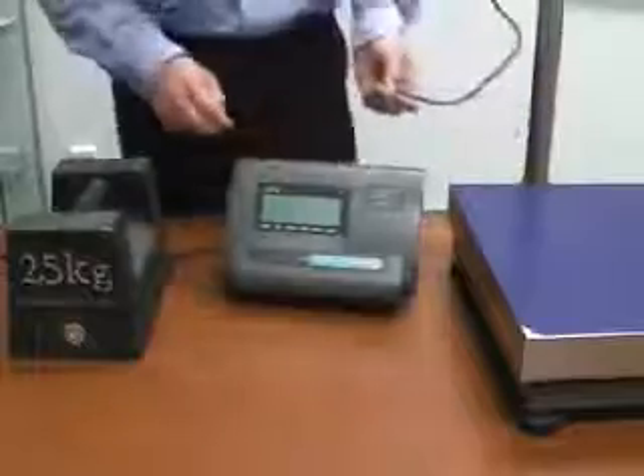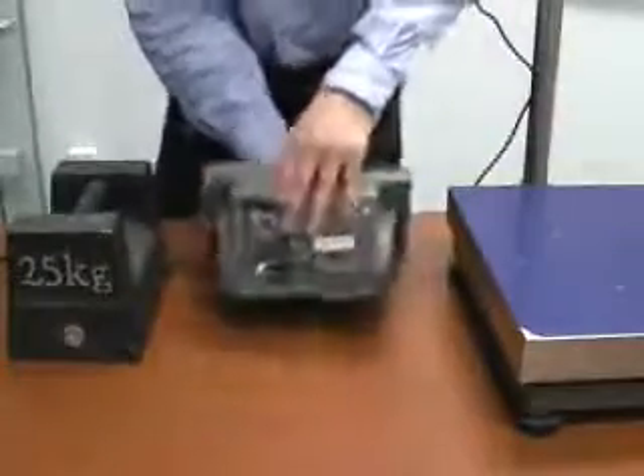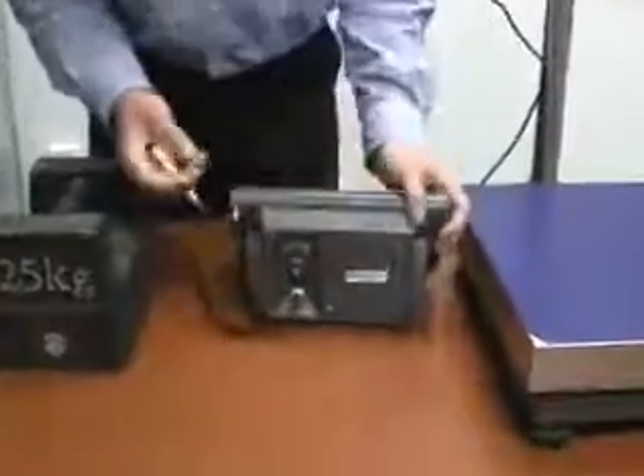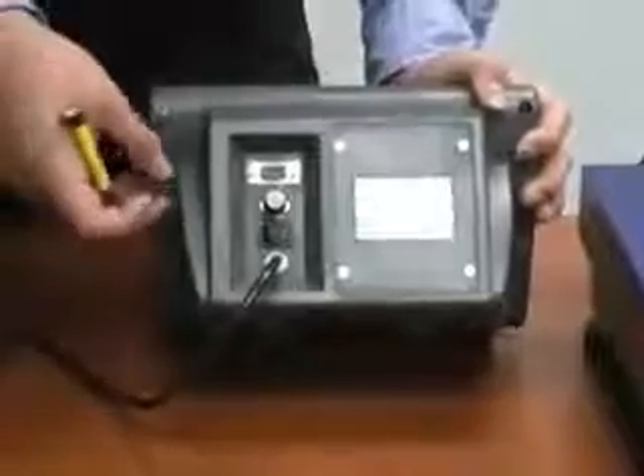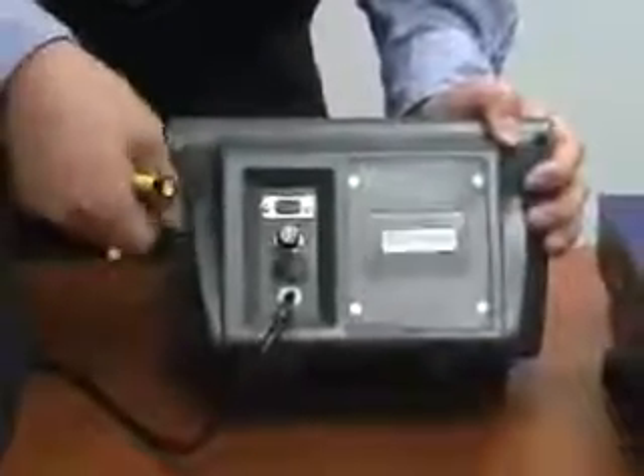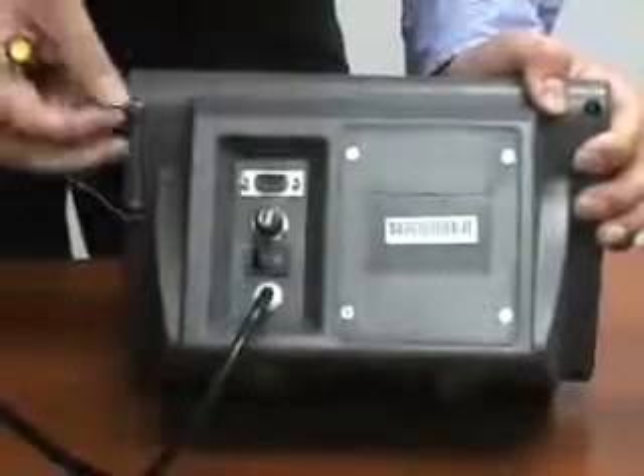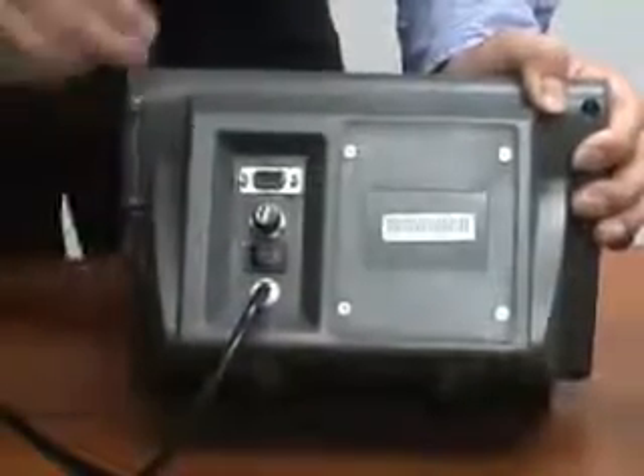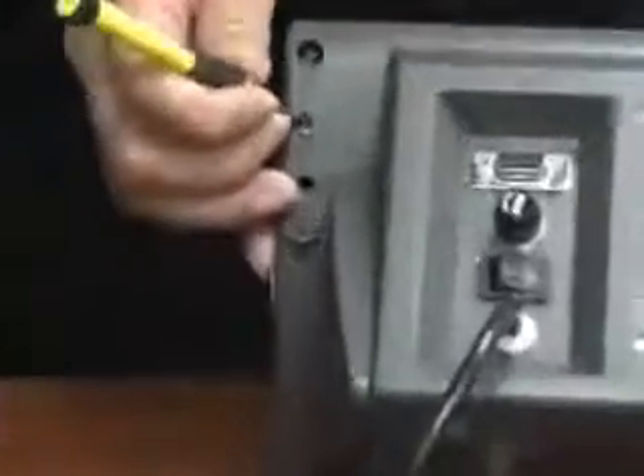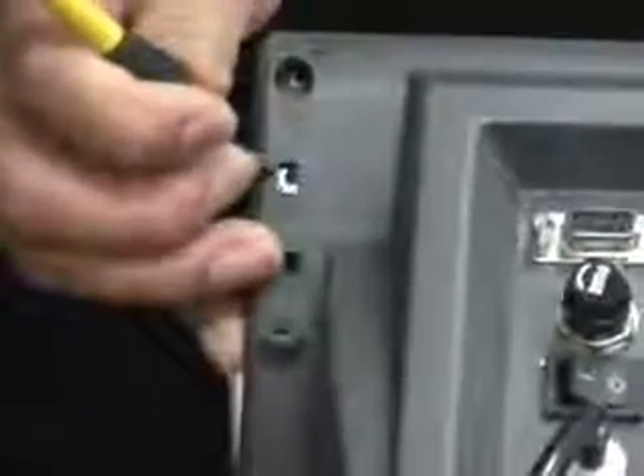First of all, disconnect the cable from the indicator and check the back of the indicator, and you will find a white seal on the back. To calibrate the scale, we need to take out the seal like this. Be careful about the sharp wire. And use a flathead screwdriver to remove this screw. And remove the plastic cover. And you will see a little button under the plastic cover. This is the calibration confirmation key. We're going to use it after the calibration.